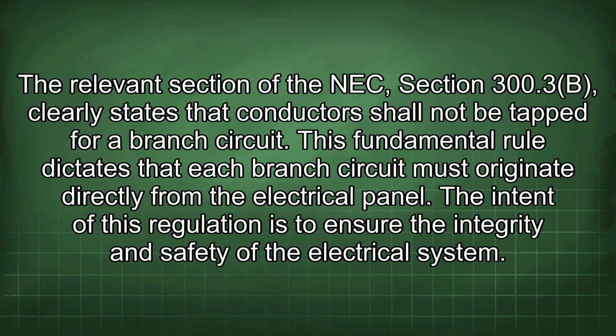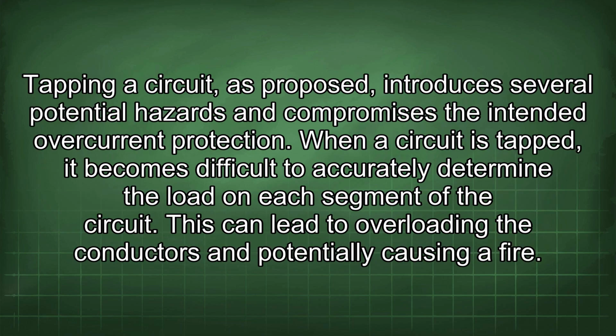The relevant section of the NEC, Section 300.3(B), clearly states that conductors shall not be tapped for a branch circuit. This fundamental rule dictates that each branch circuit must originate directly from the electrical panel. The intent of this regulation is to ensure the integrity and safety of the electrical system. Tapping a circuit, as proposed, introduces several potential hazards and compromises the intended overcurrent protection.